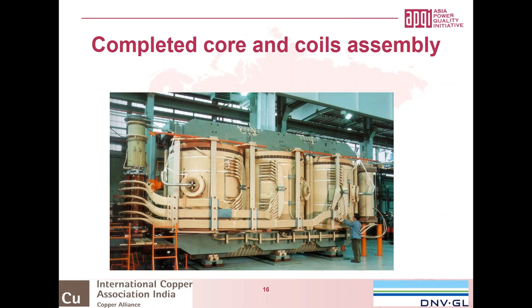If you look at the complete assembly of a transformer, this is a large transformer. You can see the guy standing on the right side. He's very small compared to this transformer. You will also see the windings on the outside. You will see the tap changer on the left side in this case. All the connections to that transformer, and right in the middle there, this is the connection of the high voltage winding within the transformer. You will also see on the upper side all kinds of construction parts to make sure that the windings are in the right spot, so that in case a short circuit current flows, the transformer will not have a failure.